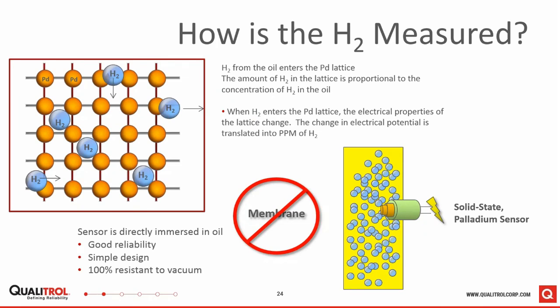I'm going to quickly go over this because I know it may not be of a lot of interest to most people on the call, but the secret behind the DGA150's performance is the sensor. And the sensor is unique, and it's ideal for two reasons. First of all, it can be directly immersed in the oil, and it can measure gas in the oil itself.